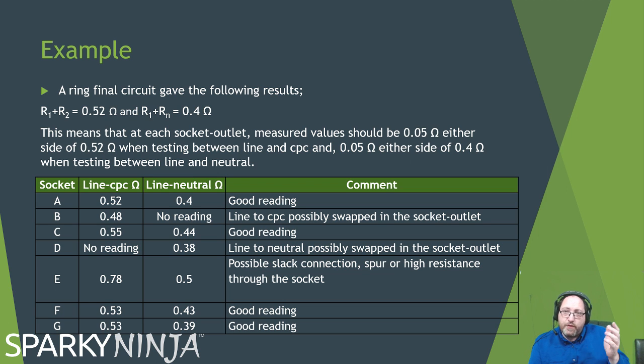Socket C, 0.55, 0.44, a good reading. Socket D, no reading for line to earth, and now a good reading from line to neutral. So no reading there, but good reading. Well, that's the opposite to B. So it's probably now that we have a line and neutral reverse.